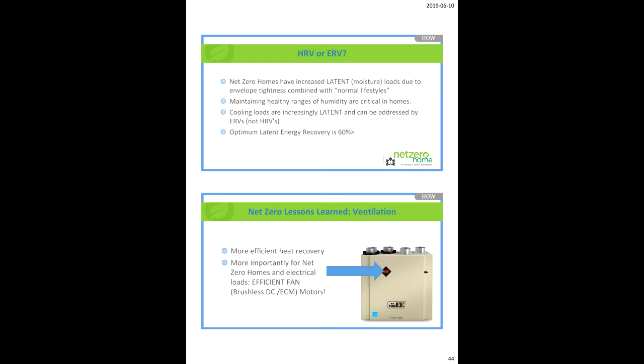So efficiency, yes - here's a quick example. In general, going from a 65% SRE to about a 90% recovery will reduce about 0.8 gigajoules on a low load net zero home. That's pretty good, not bad. But by going to ECM motors, it's a 2 GJ reduction. So again, get your efficiency up - 65, 75, that's good, get to an ERV. Next, before you go any higher on efficiency, get to an ECM motor, and then the last step is to go find that world-class 90%. But it's the motors that become the low-hanging fruit.